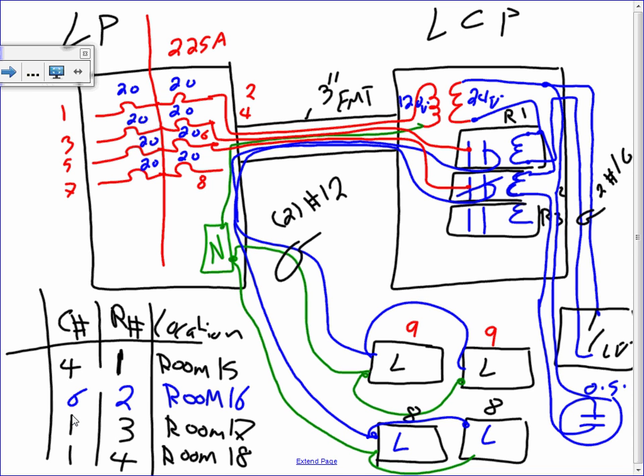But you're limited to the number of lights on each relay, aren't you? Yes, typically 18 fixtures on one circuit. How many amps can you put on a relay? Most relays are rated for 20 amps, so don't worry about them -- the relay matches the circuit breaker at 20 amps. As long as you don't exceed the circuit breaker, you're good with the relay. If the circuit breaker is good, you're good with the relay.